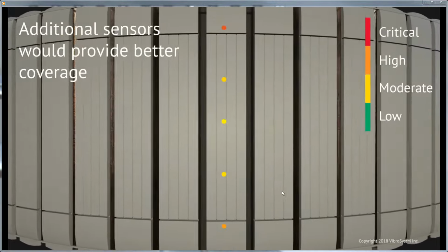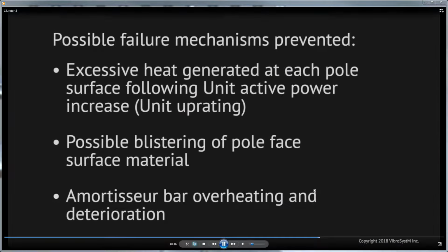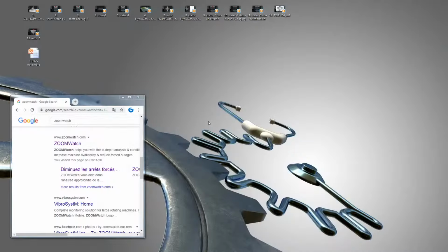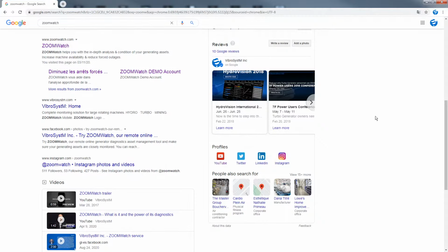Okay, so in this case, you can detect hot spots on the pole faces or on the pole joints, giving you a chance to go in and see what's going on. You can detect, again, pole face temperature issues, rotor pole joint issues. You can also see an amortisseur bar overheating. If there's an issue there, it will heat up, and you will be able to detect it with these sensors. Okay, so that pretty much covers the basic system that we recommend.